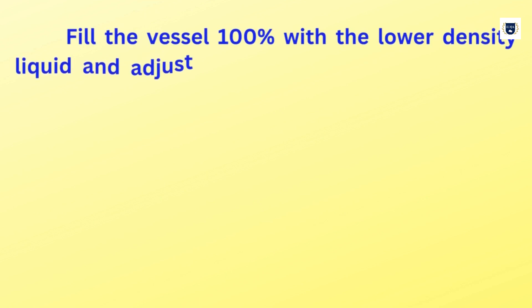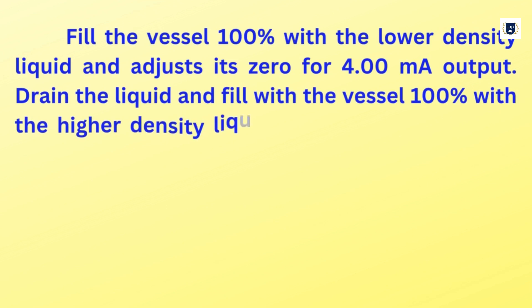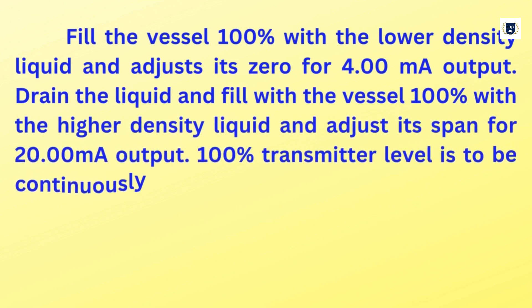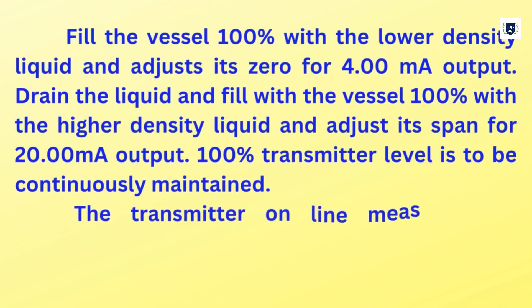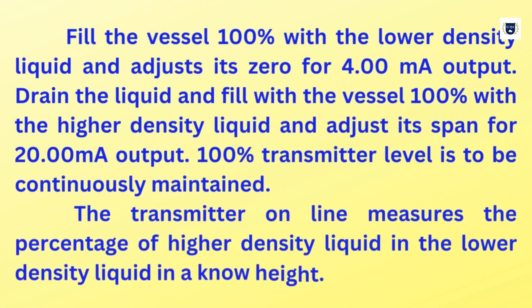Fill the vessel 100% with the lower density liquid and adjust its zero for 4 milliamps output. Drain the liquid and fill the vessel 100% with the higher density liquid and adjust its span for 20 milliamps output. 100% transmitter level is to be continuously maintained. The transmitter online measures the percentage of higher density liquid in the lower density liquid at a known height.